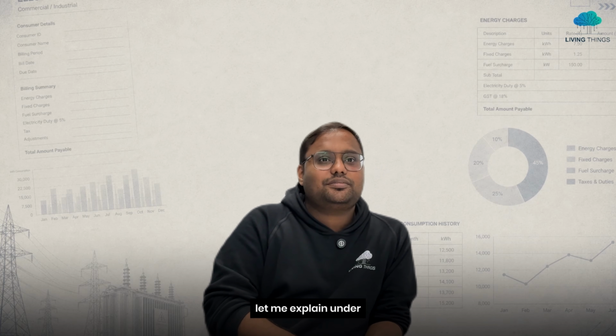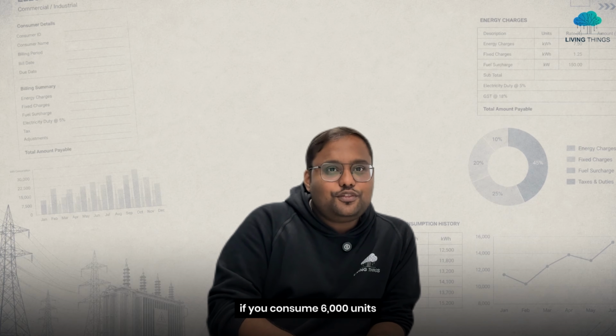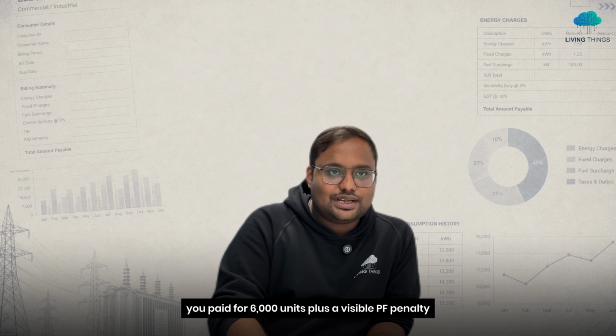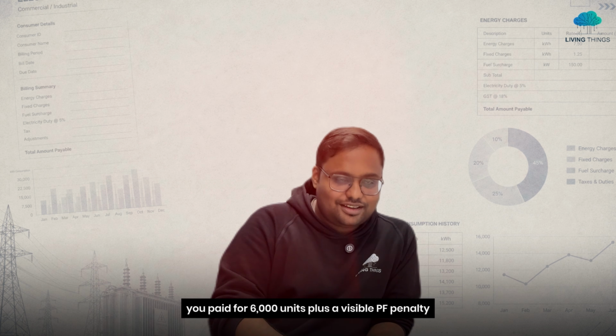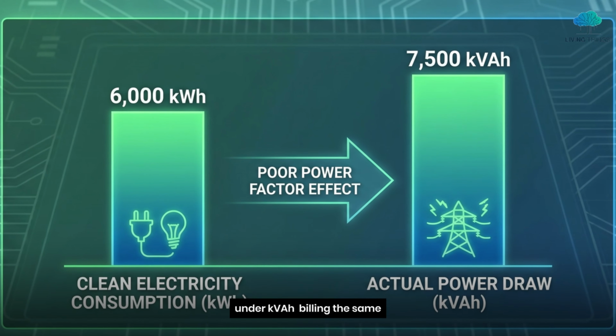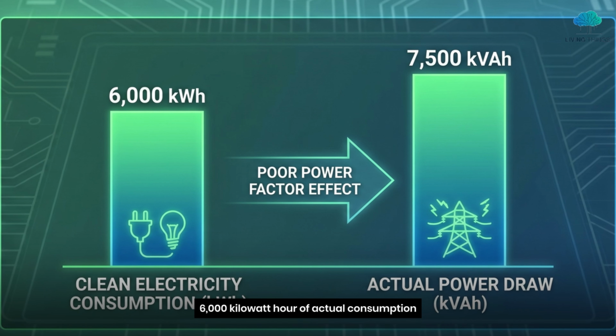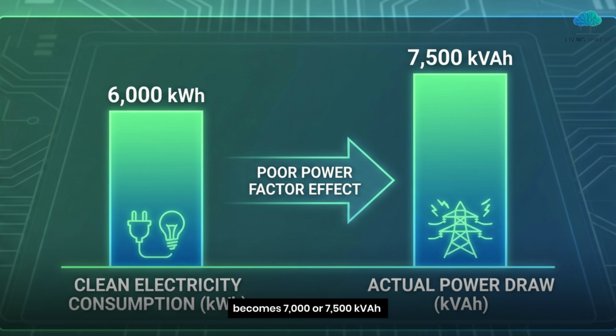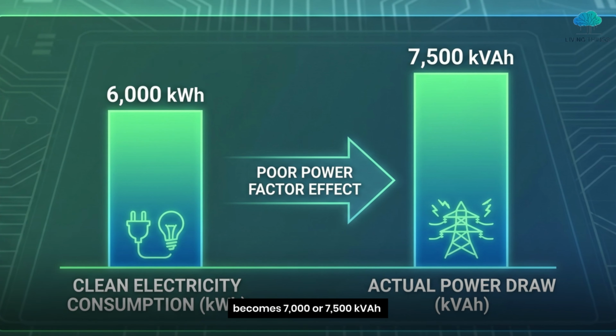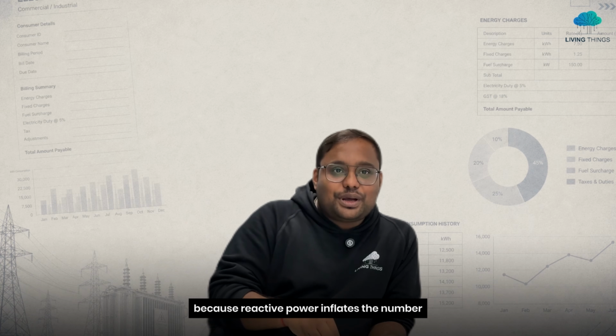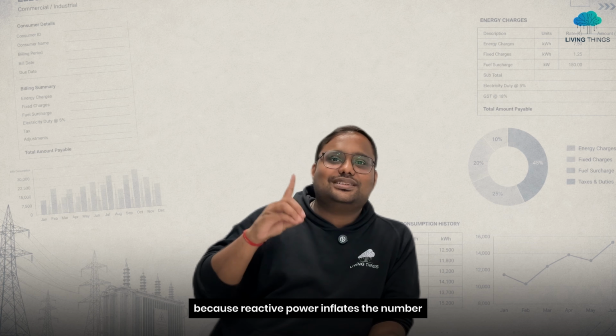Let me explain. Under kWh billing, if you consume 6,000 units, you pay for 6,000 units plus a visible PF penalty. Under kVAh billing, the same 6,000 kilowatt hours of actual consumption becomes 7,000 or 7,500 kVAh because reactive power inflates the number.